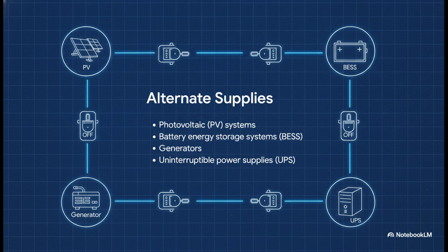The crucial point you need to remember is this: the neutral earth connection for these alternate supplies relies on the installation's main MEN connection. If you yank that MEN link without isolating these supplies at their source, you run a huge risk of energizing the neutral and earth circuits. Always isolate those alternate supplies at the source first.